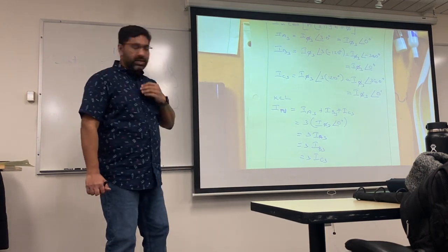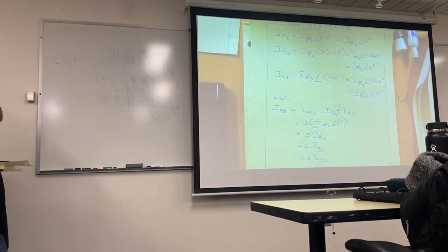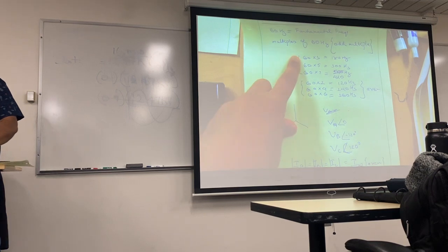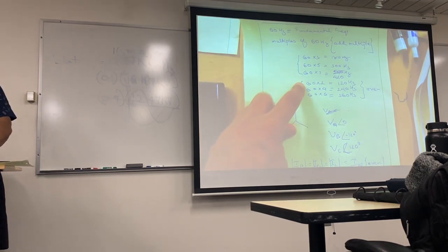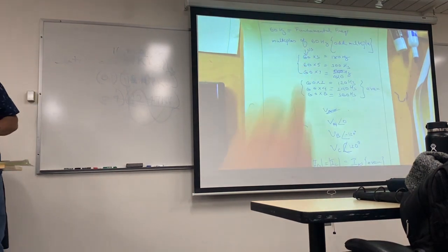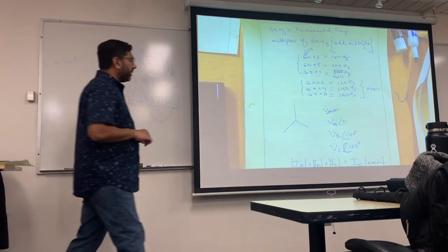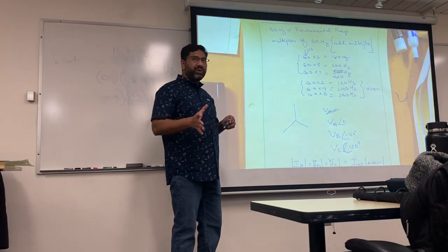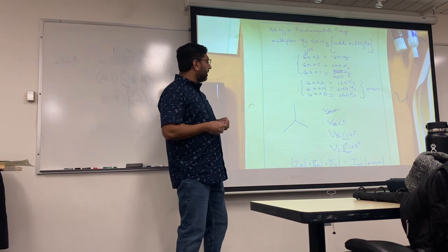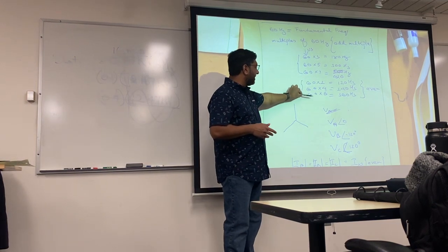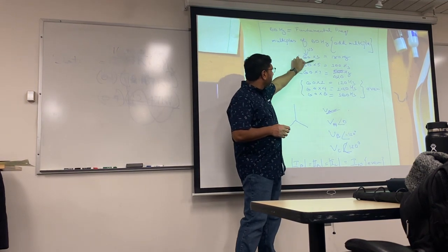of frequencies, and we discussed the odd multiples somewhere here. So if it's 60 Hertz, you're going with 180, 300, and 420. If you're looking at the even, it should be 120, 240, and 360. Keep in mind, I'm dealing with US or Canadian frequency. So if you put an oscilloscope or a spectral meter, these just cancel away. It's like they don't even exist. These guys will show up.